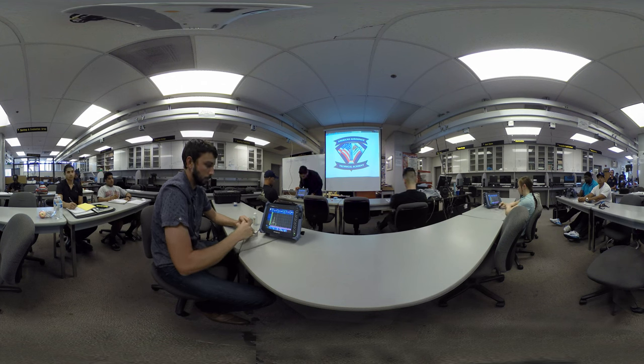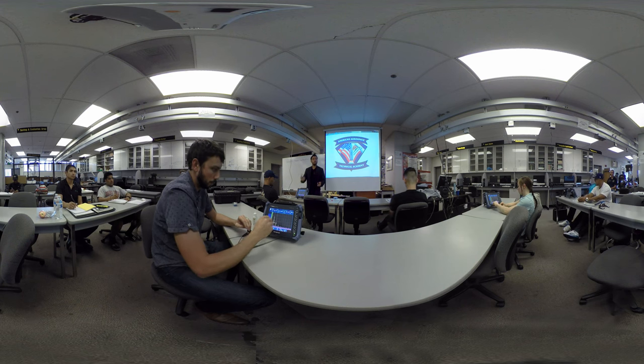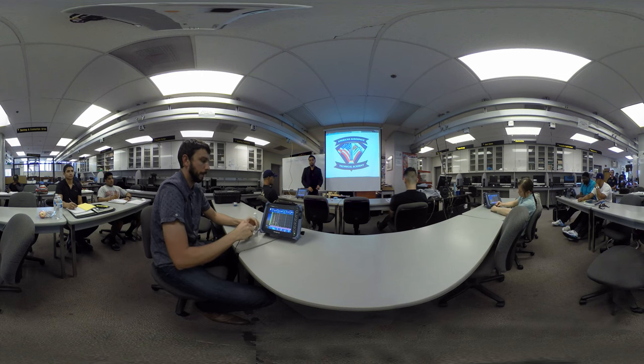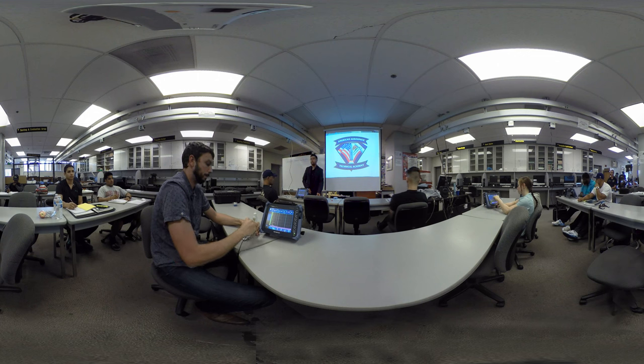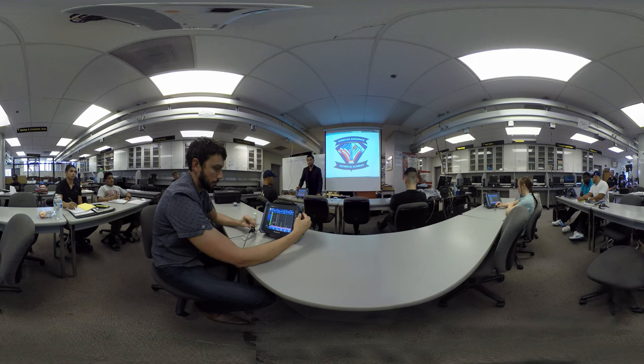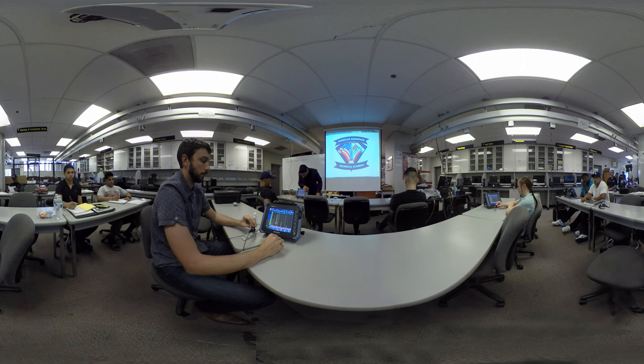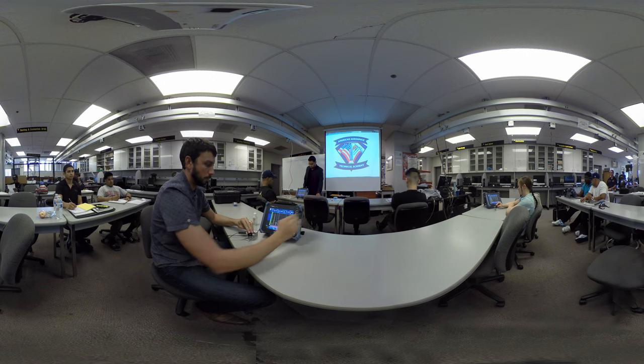Okay? Now the screen reads set gate A on thickness 2. My thickness 2 is 1 inch. So I place my probe on the 1 inch thick part. Everyone's done with half inch? Okay. So moving on to 1 inch, place the probe. Same procedure. Place the probe on 1 inch thick. You adjust the gain so that the signal height is about 80% screen height. And use the gate start and width to move the gate on the first signal after the initial pulse. Once you are done with that, click on Get Position. Okay?